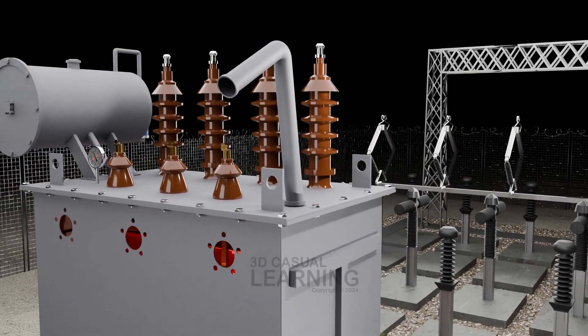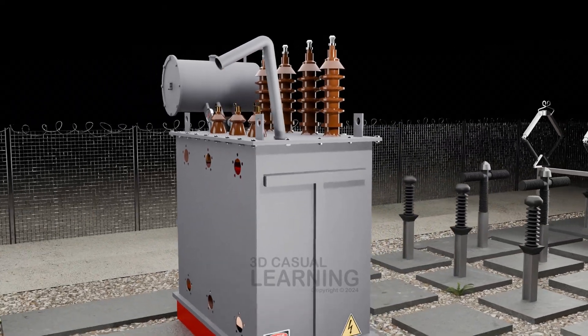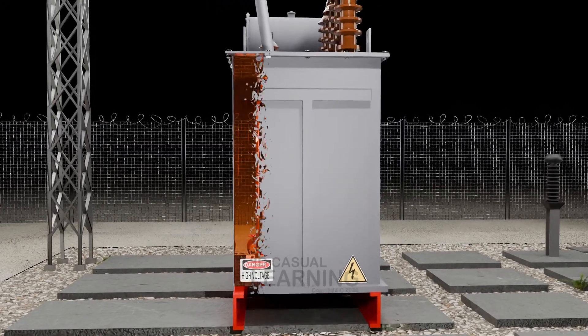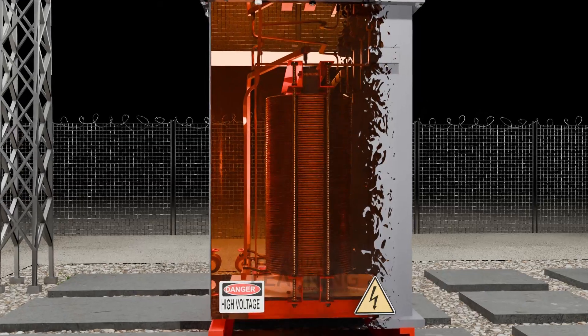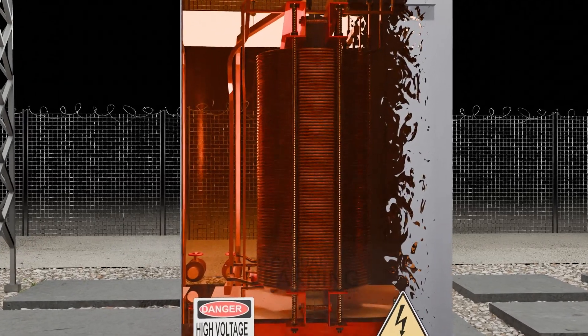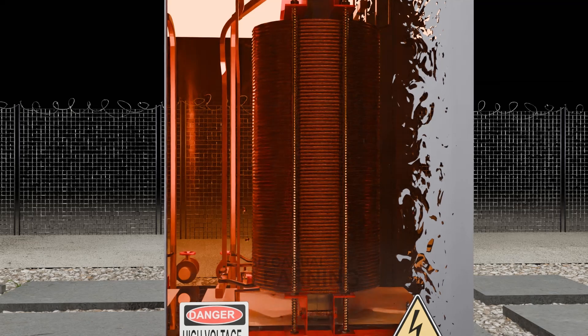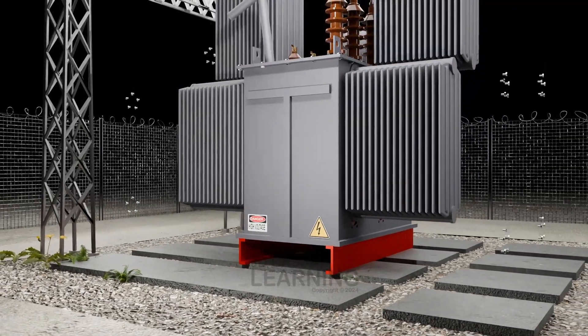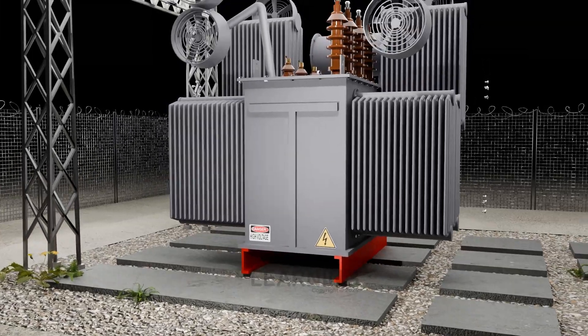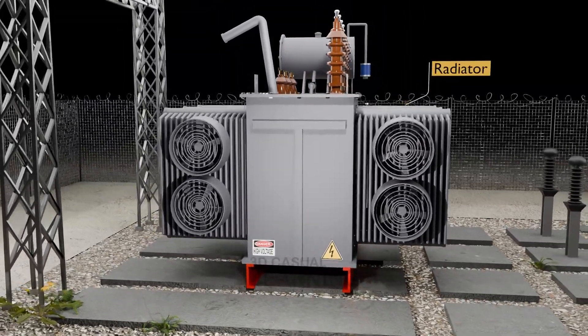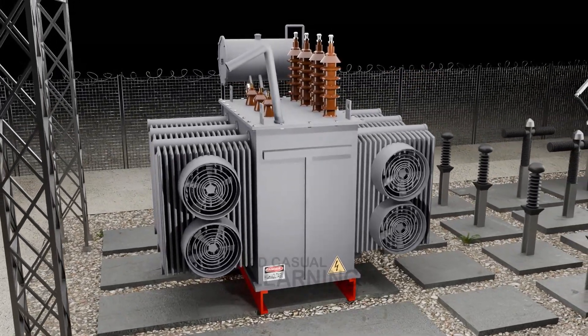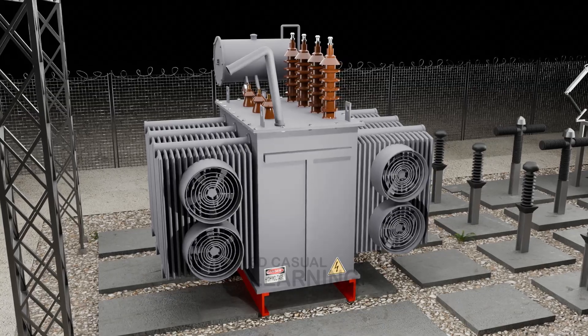Transformers generate heat due to electrical losses and magnetic flux during normal operation. This heat must be dissipated to prevent overheating, which can lead to insulation degradation and reduce transformer lifespan. The radiator facilitates the transfer of heat from the transformer oil to the surrounding air and is typically part of the transformer's cooling system, which may also include fans or natural convection. As the heated transformer oil flows through the radiator tubes or fins, it transfers heat to the metal surfaces, which in turn transfers it to the surrounding air, lowering the temperature of the transformer oil and internal components.